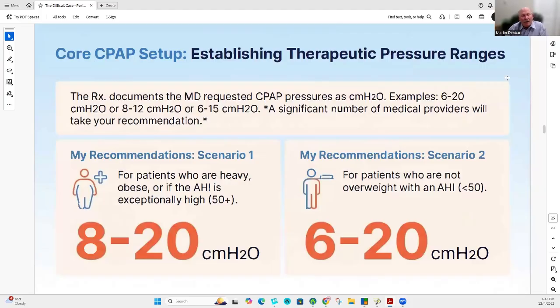But when you have someone that's heavier, or with a high AHI or a real low SpO2 oxygen level, I'll go 6 to 20 or 8 to 20. Now, once again, I always use a 4 centimeter ramp. So if they're at 8 and they say it's just too high, you hit the ramp, which drops them to 4. I've found 15 minutes for the ramp time is kind of a sweet spot, but do it at 30 if you're comfortable with it. I've just found 15 normally works well.